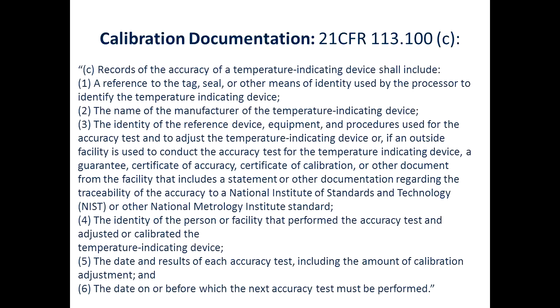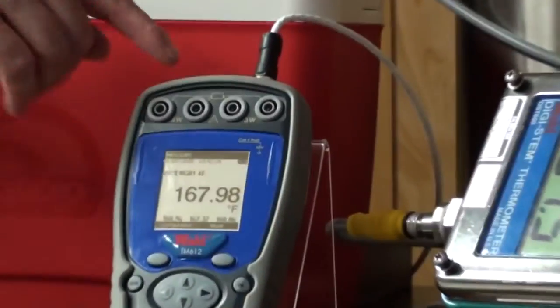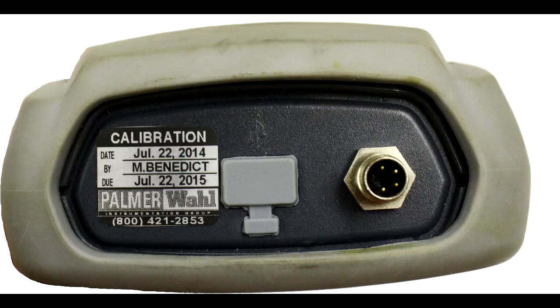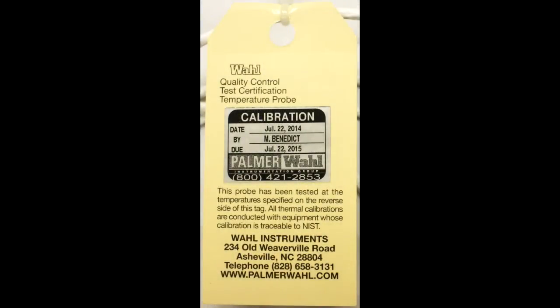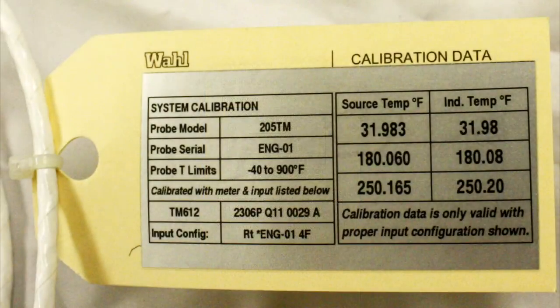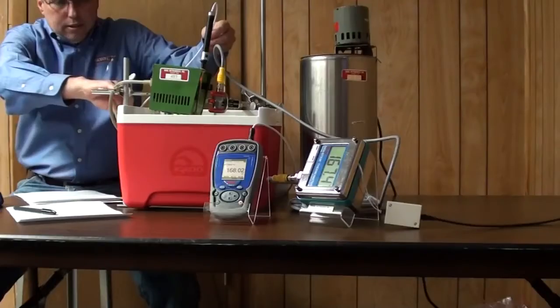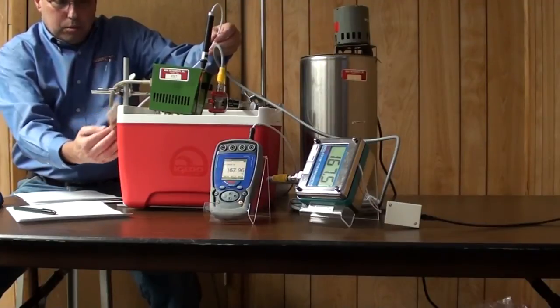The 113.100 paragraph, and I won't go through everything, is for the temperature indicating device, and it basically says you need a tag, seal or other means of identity. You can't see it, but on the top of ours we have a serial number tag, a calibration tag, things like that. There is a tag on our probe here, and that also has a calibration tag, which tells you the due dates of the calibration. I'm going to slide that down here so it doesn't fall in my hot water bath there.